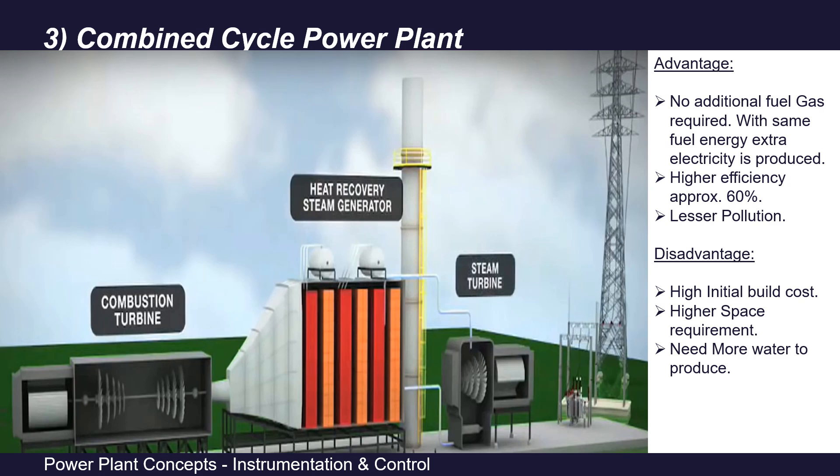The advantages of a combined cycle power plant: no additional fuel gas is required — fuel gas is only fed in the Brayton cycle to rotate the gas turbine — so with the same fuel energy, extra electricity is produced. These power plants have a higher efficiency of approximately 60%. As the exhaust gases are already cooled, there is lesser pollution. The disadvantages are higher initial building cost, more components requiring higher space, and a need for more water to produce steam.